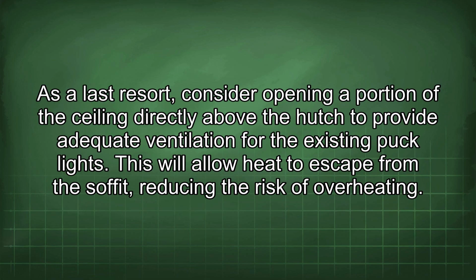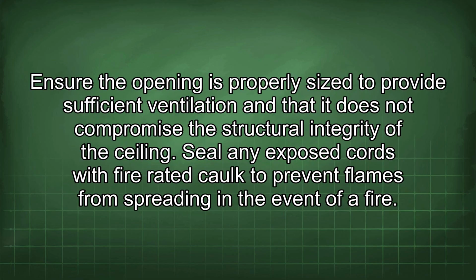As a last resort, consider opening a portion of the ceiling directly above the hutch to provide adequate ventilation for the existing puck lights. This will allow heat to escape from the soffit, reducing the risk of overheating. Ensure the opening is properly sized to provide sufficient ventilation and that it does not compromise the structural integrity of the ceiling. Seal any exposed cords with fire-rated caulk to prevent flames from spreading in the event of a fire.